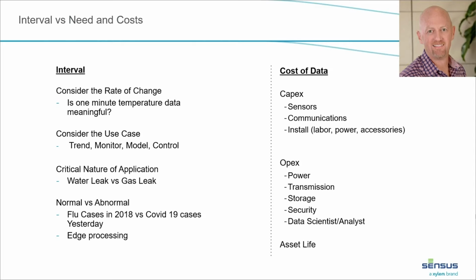You have to consider the rate of change. For example, is 1-minute temperature data meaningful? It might be if you're controlling a steam boiler. It probably isn't if you're controlling a water utility pipeline or service line—you might only need hourly, daily, or 4-hour buckets. Again, consider the use case: trend, monitor, model, or control, because they all have different values associated with them.